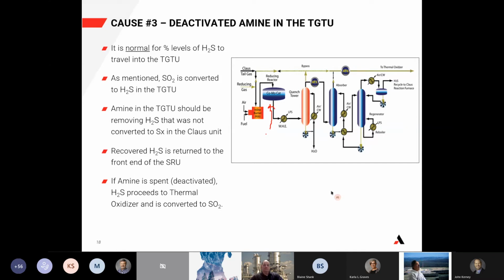But what is the benefit if we go quench outlet? What can we do there? At the quench outlet, we should ask the question, should we not measure the H2S at the quench outlet as well? You may ask, why should I do that? The point is, how do we know when the absorber H2S goes up or down? How do we know what is the cause of that? For example, you see a steady increase of the H2S at the absorber outlet. So what do you do?